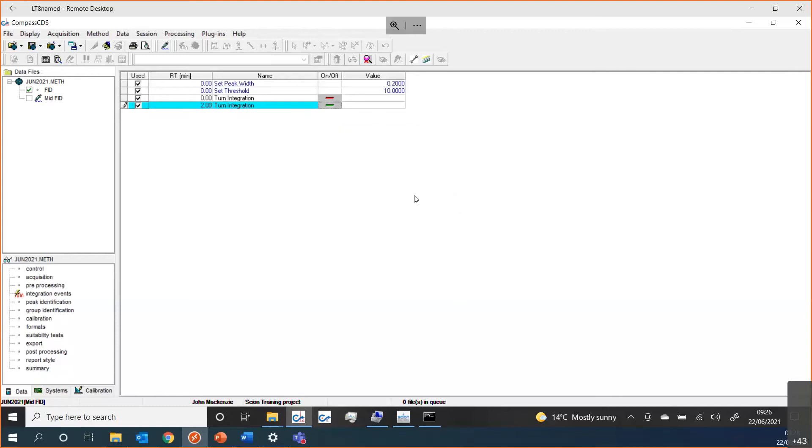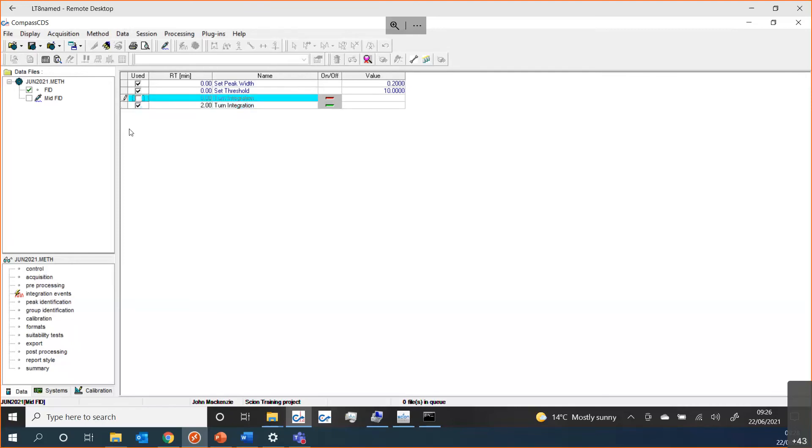You can build up a very long or a very complex time program adding all of these different events depending on what your chromatography looks like and the difficulties that you may have with your separations. These are very helpful tools and very useful. We have quite a nice feature if you build up a long list of these where you have lots of different events. Sometimes or some samples you may not want to use them. You want to collect all of the data or you want to collect the data in a different way. What you can do is you can leave them on the list. You don't need to delete them. You can just disable them just by unticking. Then that feature is not used anymore. It's still on your list. And when you need it back, it is a simple case of coming back in, turning it back on and you're ready to go. Very flexible, very versatile, very quick to make changes.